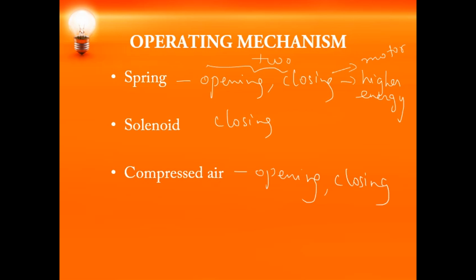When you have an oil circuit breaker, a solenoid is used for closing and a spring is used for opening. Whereas for medium sized circuit breakers, where provision of a battery for a solenoid is not possible, a spring is employed for both closing as well as opening. And in an extra high voltage oil circuit breaker, compressed air will be used for closing and the spring will be used for opening. The spring has to be pre-charged before either opening or closing. In the case of air blast circuit breakers, we use compressed air for both opening as well as closing. And in the case of SF6 circuit breaker, compressed air is used for closing and spring is used for opening, or you can use compressed air for both closing as well as opening.